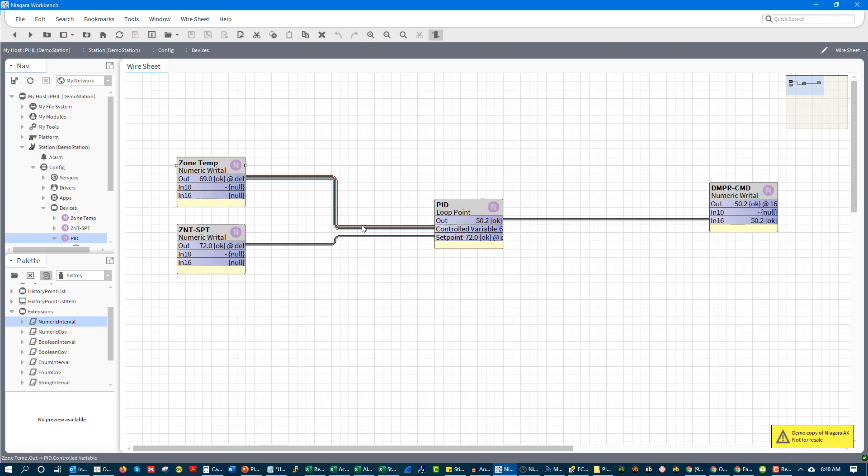And if I, once again, command it down to 69, you're going to see that drop another 10%. That's your proportional. And you see that it starts ticking down faster and faster. And that's because your integral does two things.